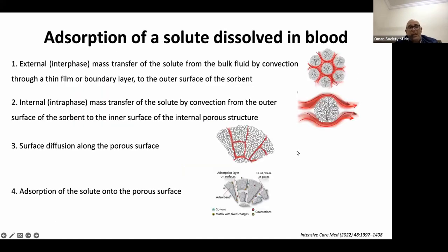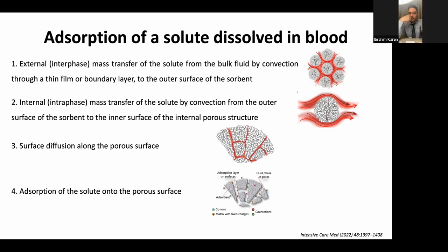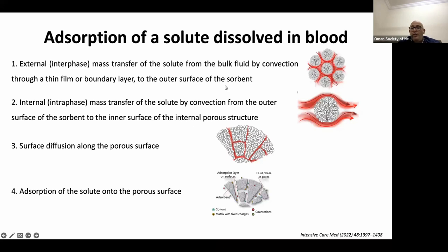Adsorption is based on four steps: first, the interphase step — external and dependent on convection — as blood passes through the film or boundary layer to the outer surface of the sorbent; second, the intraphase step, where solutes move by convection from the outer surface of the sorbent to its inner porous structure; third, diffusion along the porous surface; and fourth, the actual adsorption of the solute through the porous surface.